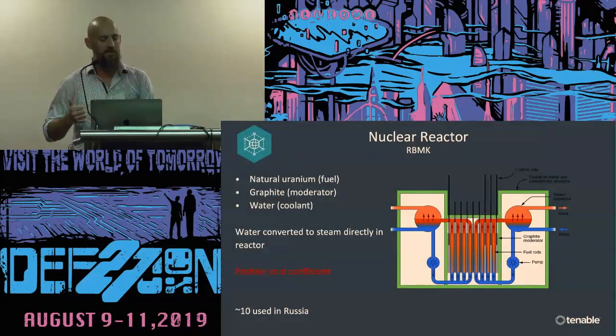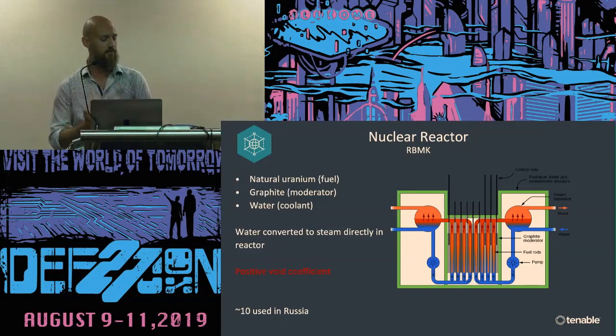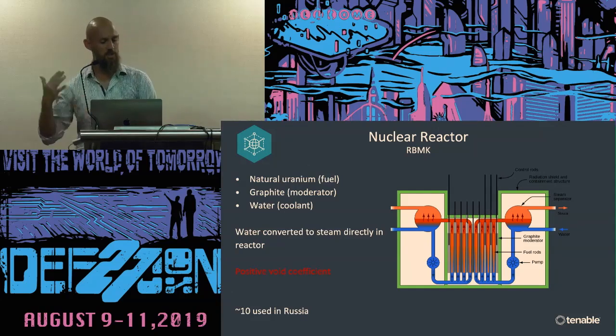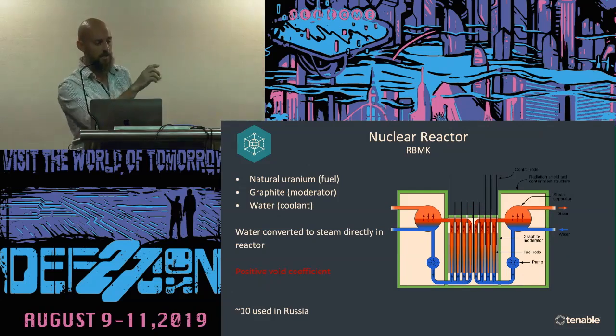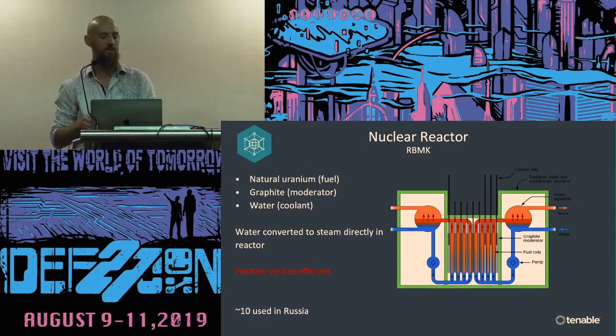The last reactor type we have to mention is the Russian RBMK — a horribly unstable design. There are still about three of them in Russia. They use natural uranium, so as temperature goes up, uranium reactivity increases. It uses graphite as a moderator and water, and has a positive void coefficient — meaning as the liquid in the core boils off and creates steam between the fuel rods, reactivity increases. As heat goes up, reactivity goes up — that's basically why Chernobyl exploded. Russia has started putting in PWRs over the last decade but still has some of these in action.